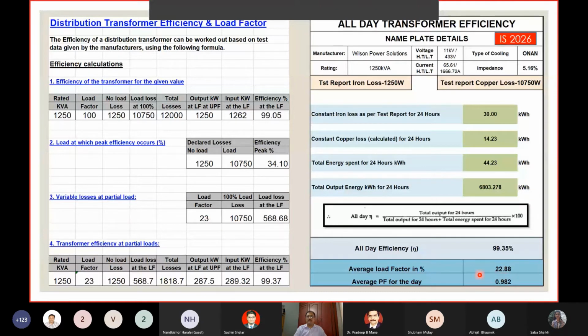So if you consider 23% as a load factor and find out what is the I-squared R loss, you will find that from 10,750 watts, it has come down to 568 watts because of the low loading. So at 23%, the transformer efficiency is 99.37%. So these two figures will more or less agree. This is a static value, which is a fixed specification, but this is a dynamic value for a full day, the all-day transformer efficiency.